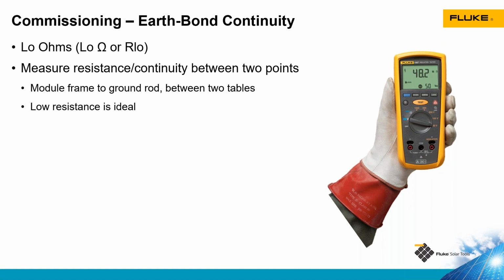Another test that's done at commissioning is earth bond continuity testing. This is measuring between 2 points of metal equipment to make sure that they are electrically connected together. And I can really do this test between any metal parts in the system that are non-current carrying. So it could go from my module frame to the racking, from the module to the ground rod, between different sections of racking, referred to as tables in many cases. Any metal parts that are connected that should be electrically connected together, I can test for it.